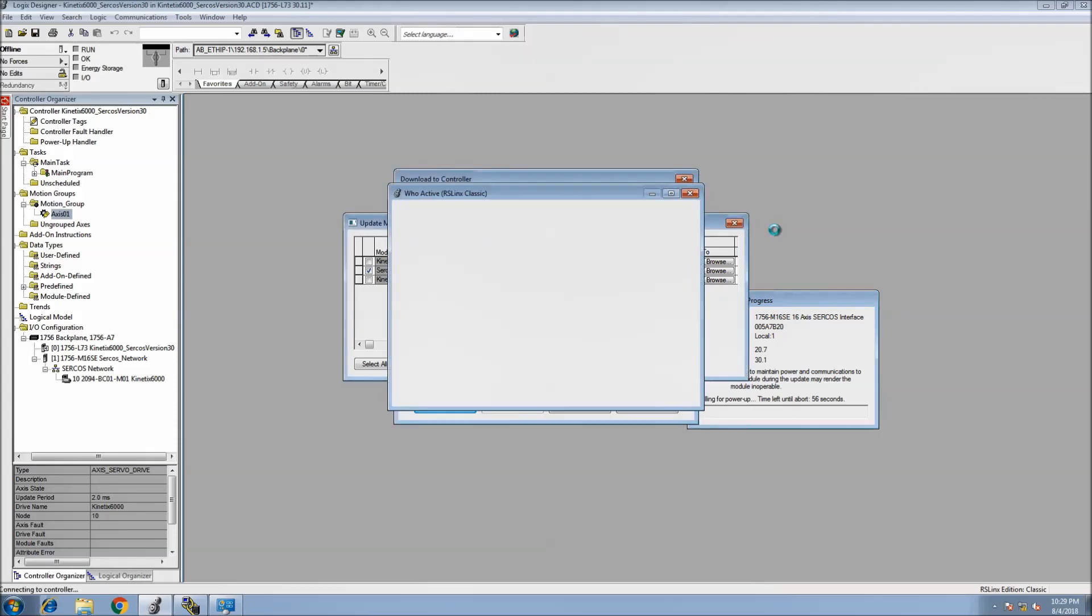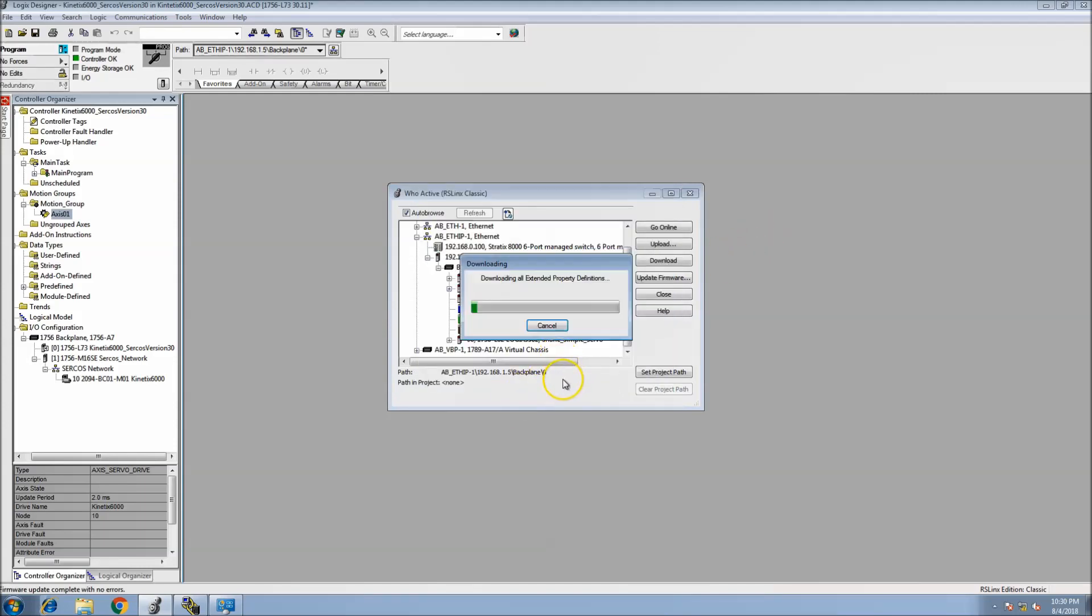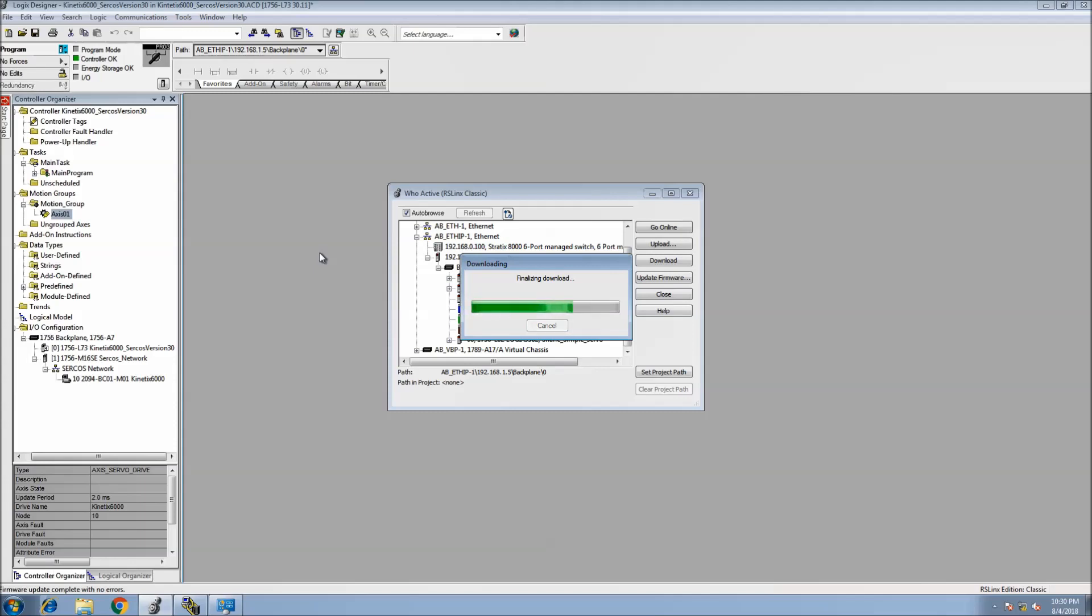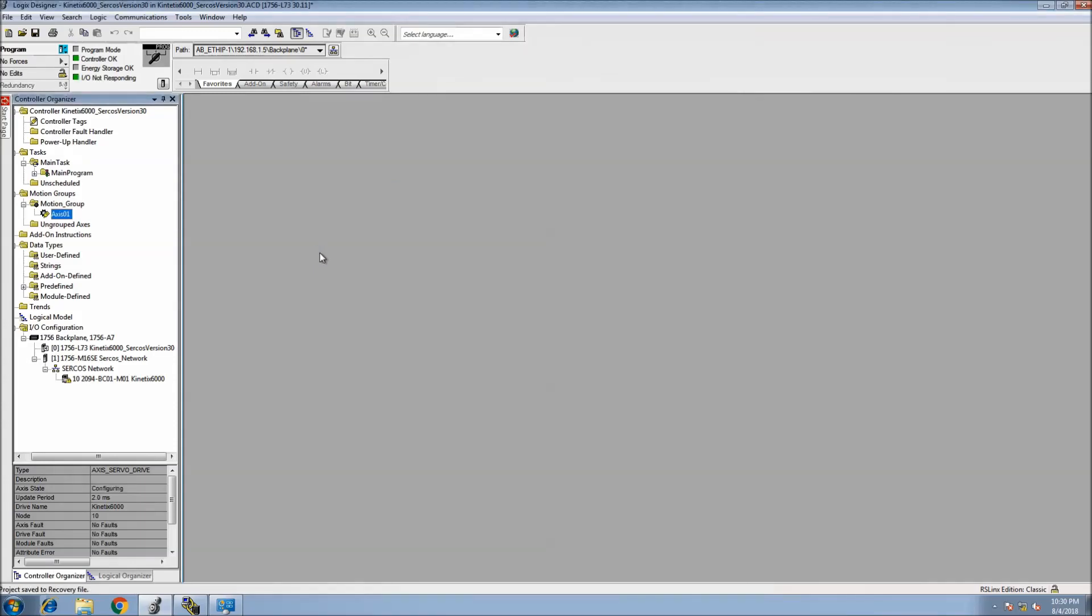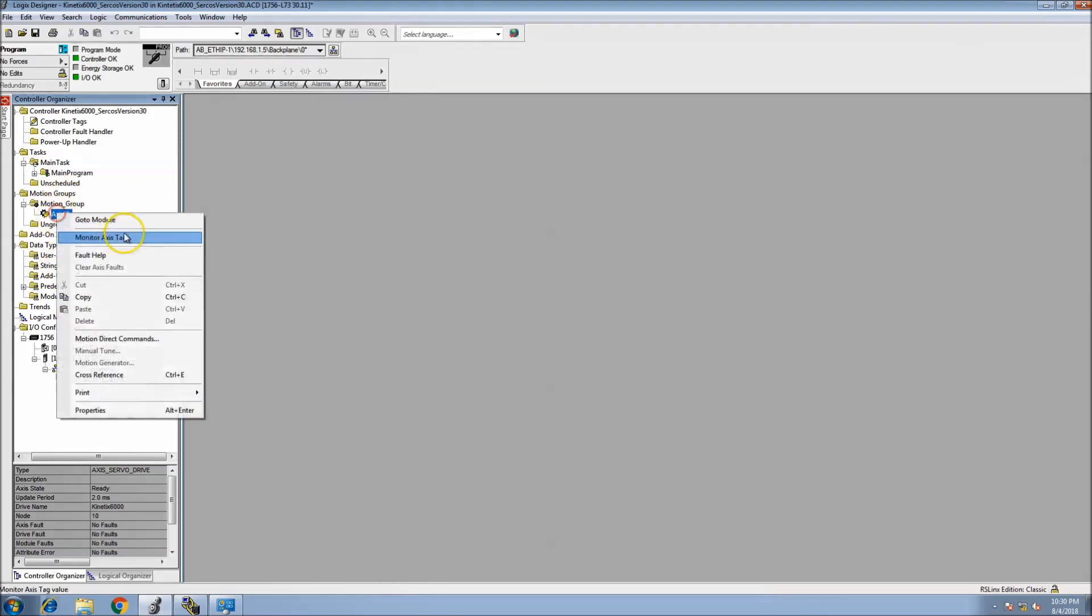As soon as the SERCOS card matches the processor, then everything should be good to go. That's one thing that's really critical - that your SERCOS card is in line with your processor, meaning your firmware to firmware is right, or else it will fault and you're not allowed to download or it won't work correctly.